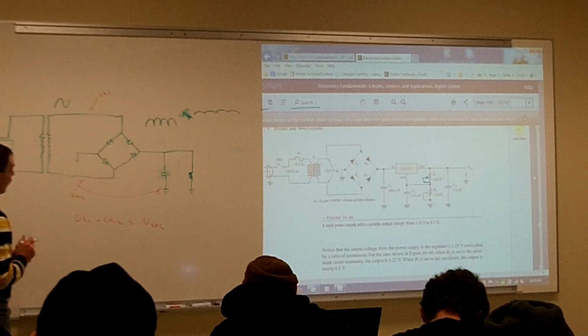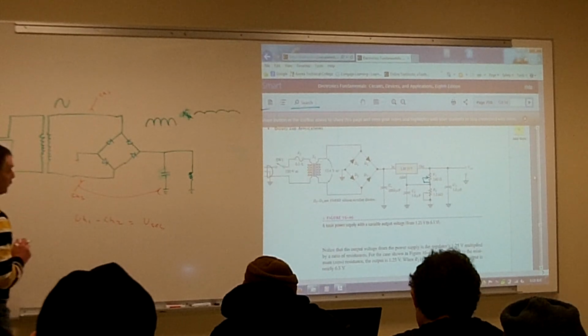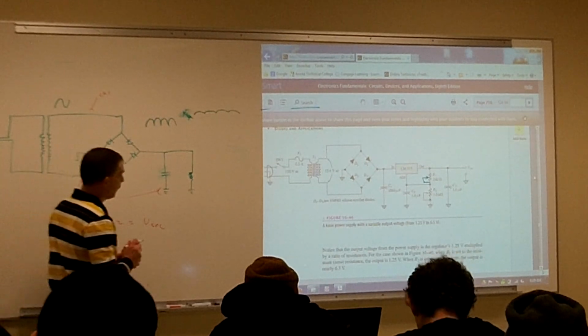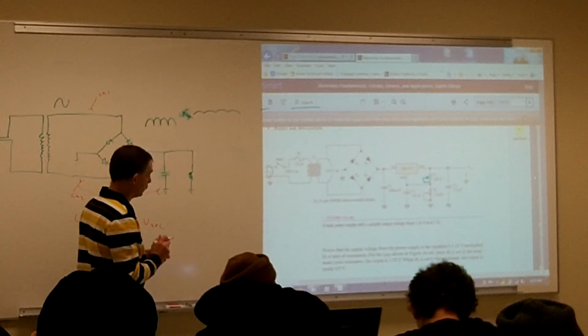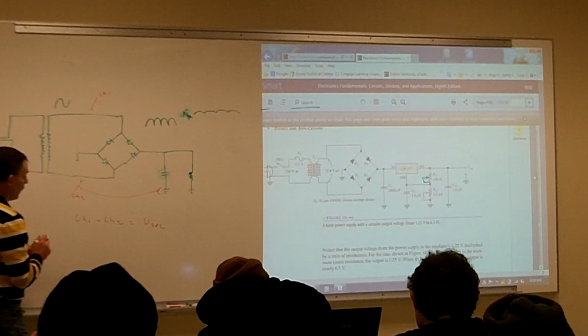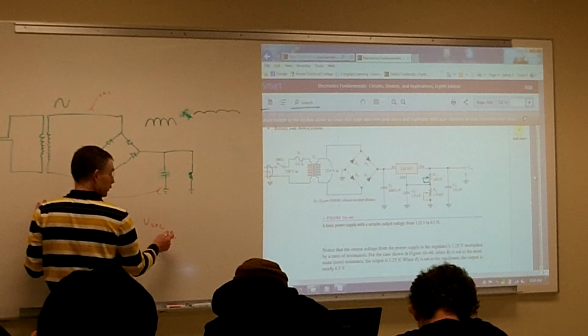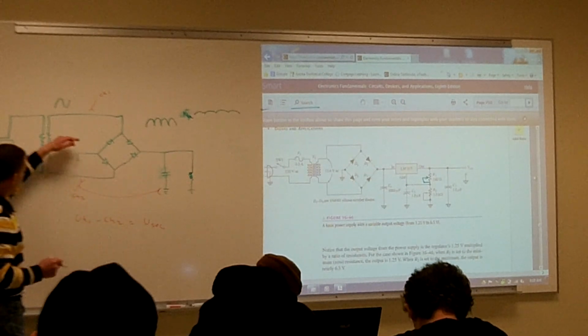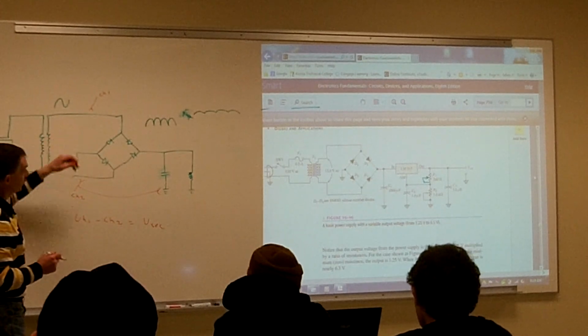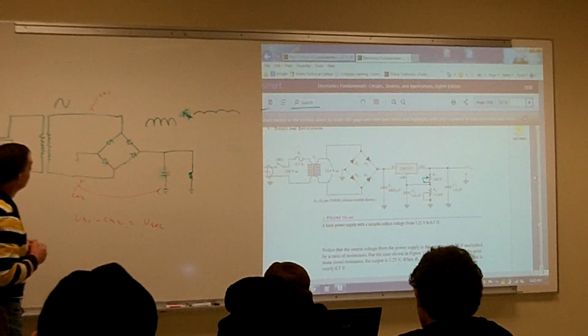Without a load on there, it's probably going to read about 14 volts AC. With a load on there, it'll get closer down to 12.6 volts AC. But when you start putting the load on, that voltage across the secondary will start to drop, so be careful of that when doing your measurements across your secondaries.